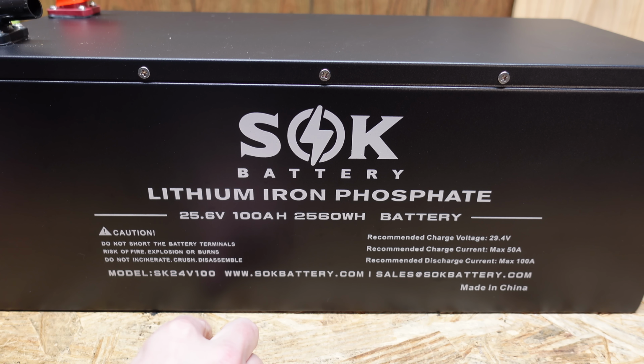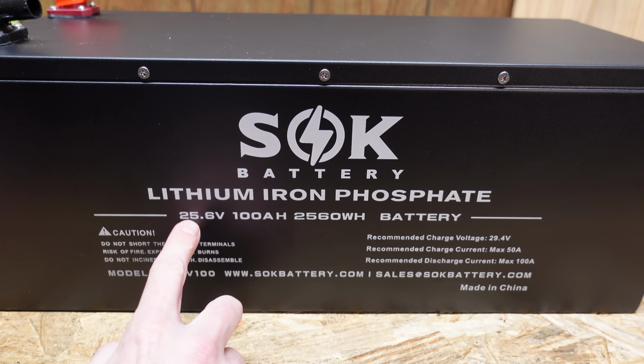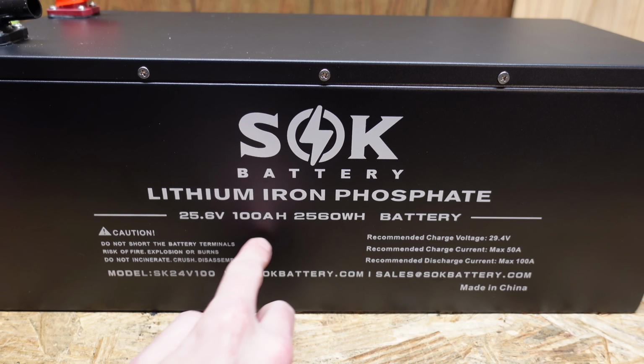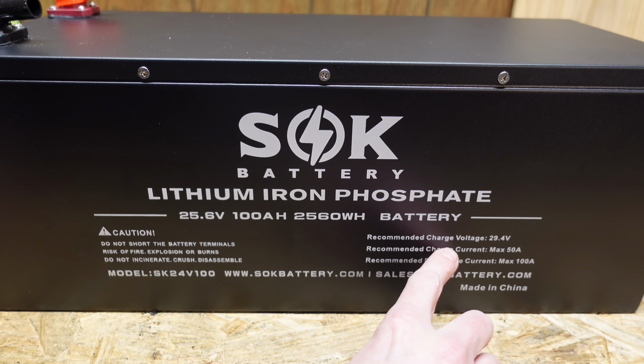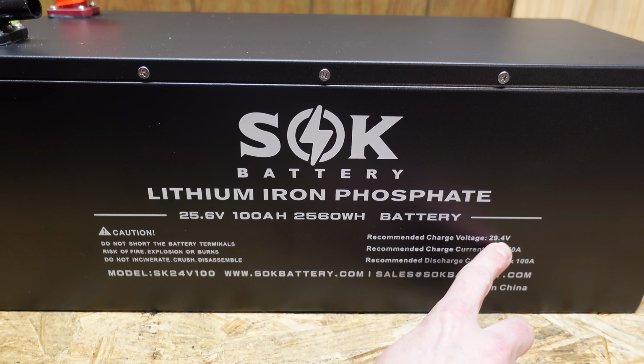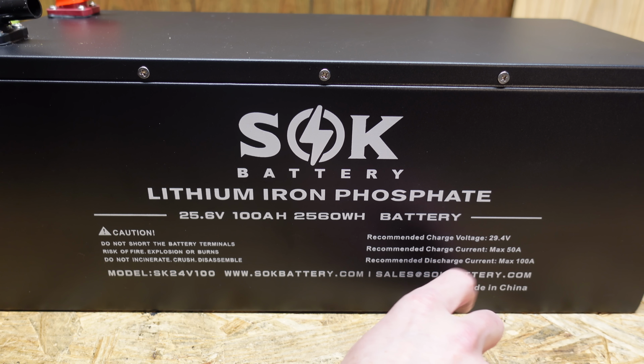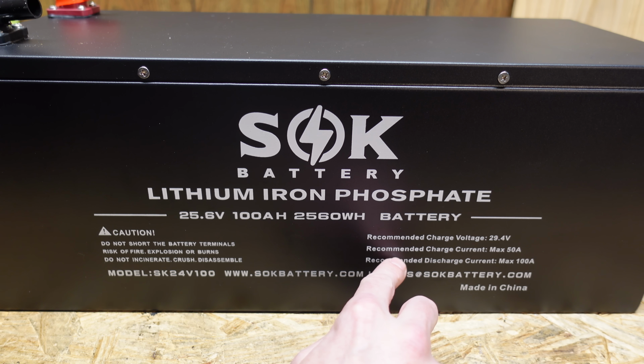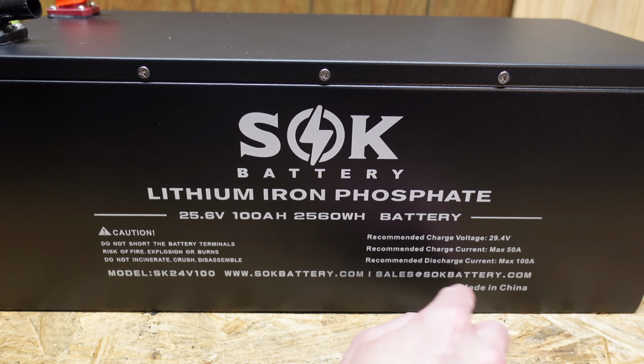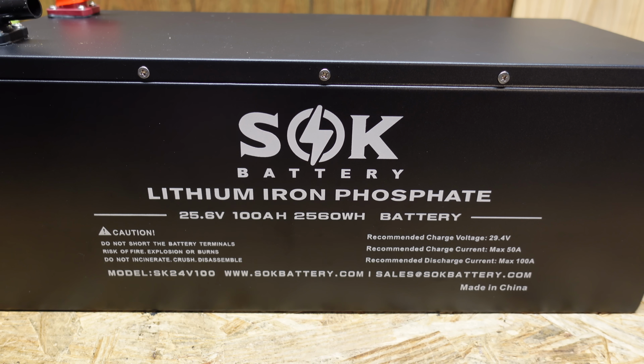On the front we can see some quick specifications. Again, 25.6 volts nominal, 100 amp hours. We've got a recommended charge voltage of 29.4 volts, which comes out to 3.67 volts per cell, so I suppose that allows a little room for balancing at the top end. We have a recommended charge current of 50 amps and a recommended discharge current of 100 amps.